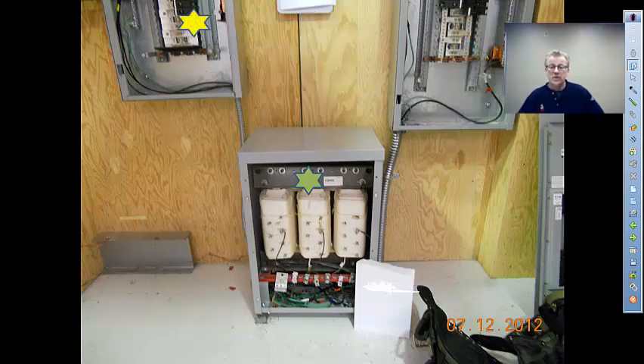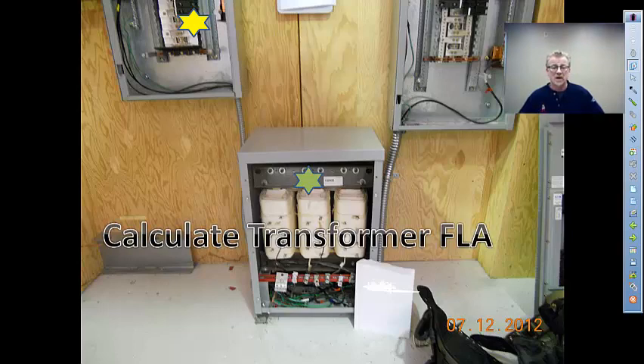So the first step we're going to do is start looking at that feeder breaker, the primary breaker. It might be the high voltage side, might be the low voltage side. Transformers are bidirectional devices, might be a step up or a step down. In this case, we're talking about a 480 volt primary and a 208 volt Y secondary, sort of your typical commercial building kind of a setup. Calculate the transformer's full load current.